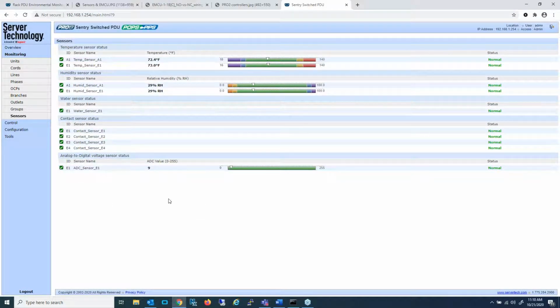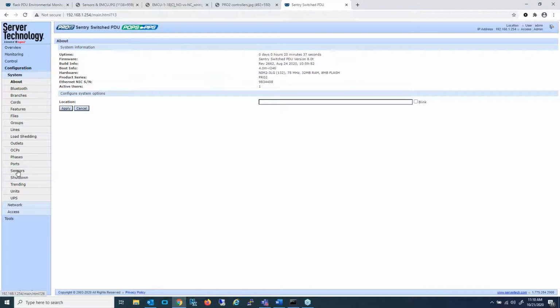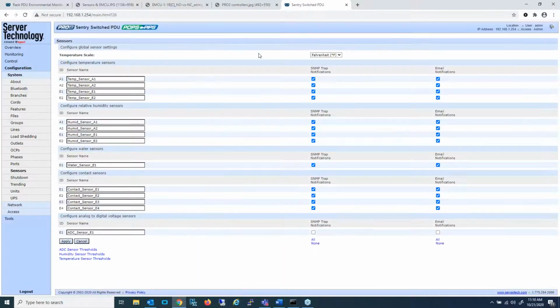At this point, we're going to take a look at where to configure the unit of measure and additional items, and that's going to be under configuration. You need to locate sensors, and here we are. This is the primary page for configuring whether or not you receive SNMP notifications or email notifications. You can change the names of the temperature sensors and the humidity sensors, water sensors, contact closures, and the analog digital channel. You can also change your scale, unit of measure, if you will, for the temperature. I'm going to just leave that at Fahrenheit. Down here at the bottom is where we find links for configuring the thresholds.